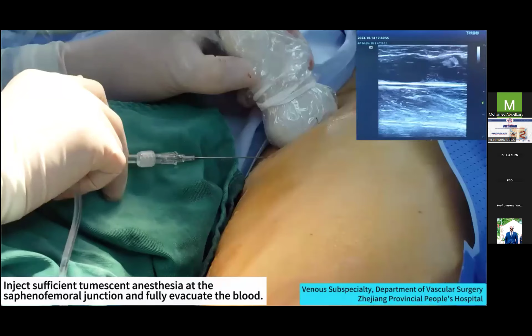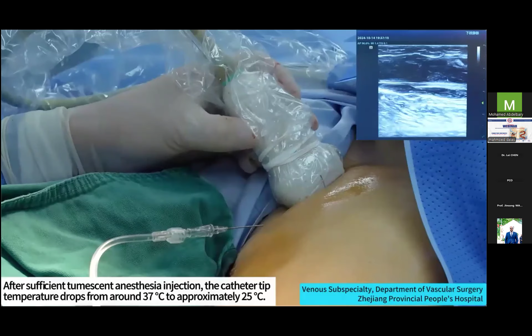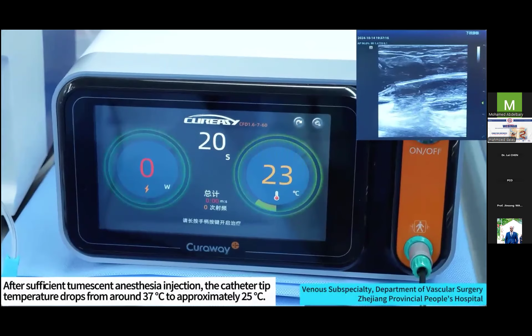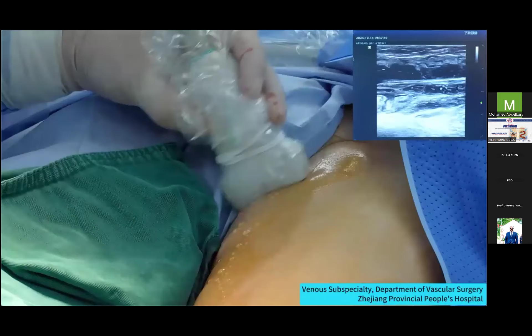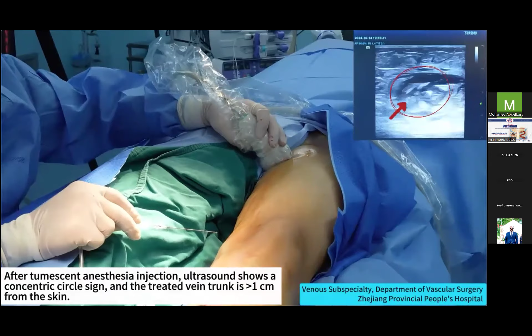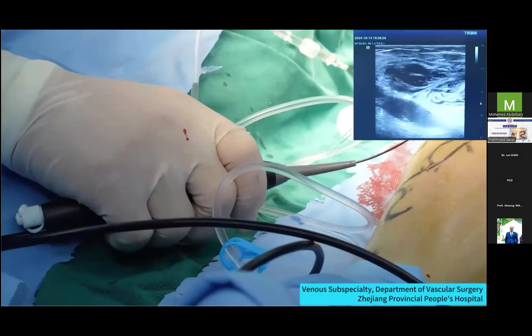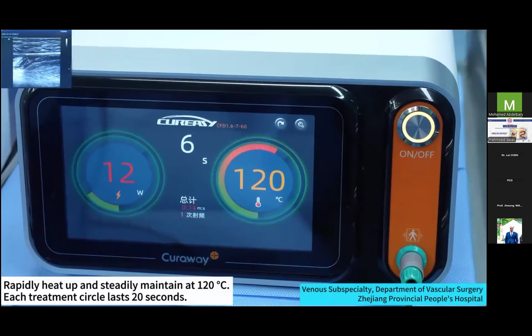Inject sufficient tumescent anesthesia at the saphenofemoral junction and fully evacuate the blood. After sufficient tumescent anesthesia injection, the catheter tip temperature drops from around 37 C to approximately 25 C. After tumescent anesthesia injection, ultrasound shows a concentric circle sign, and the treated vein trunk is more than 1 cm from the skin. Reconfirm the catheter tip position and start the radio frequency treatment. Rapidly heat up and steadily maintain at 120 C. Each treatment cycle lasts 20 seconds.